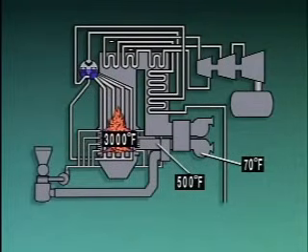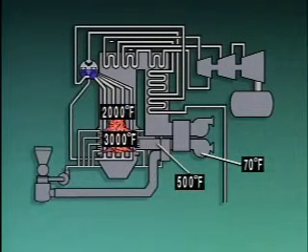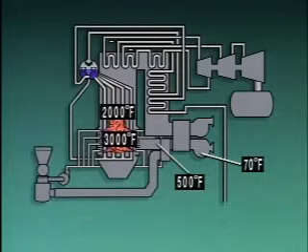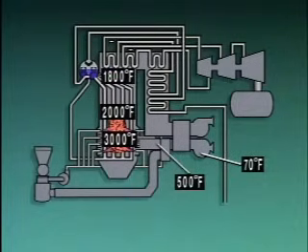The chemical reaction of combustion consumes most of the oxygen in the air and produces hot combustion gases, which flow out of the boiler furnace. As the combustion gases rise in the boiler furnace, their temperature decreases to about 2,000 degrees Fahrenheit as heat is absorbed by the tubes surrounding the furnace. By the time the combustion gases enter the area of the gas flow path containing superheaters and reheaters, their temperature has dropped to about 1,800 degrees Fahrenheit.